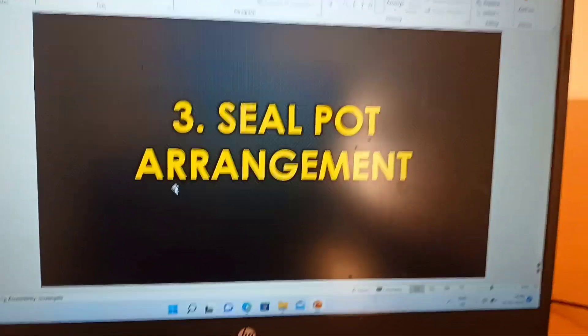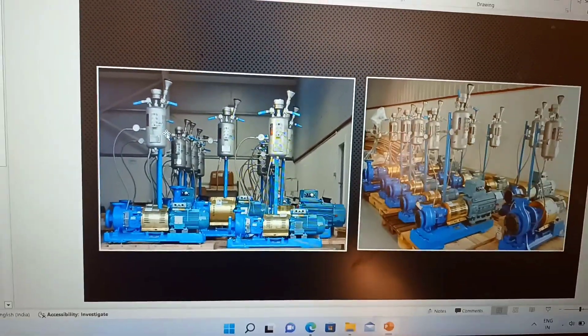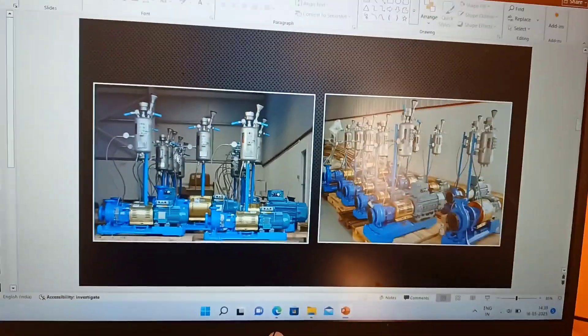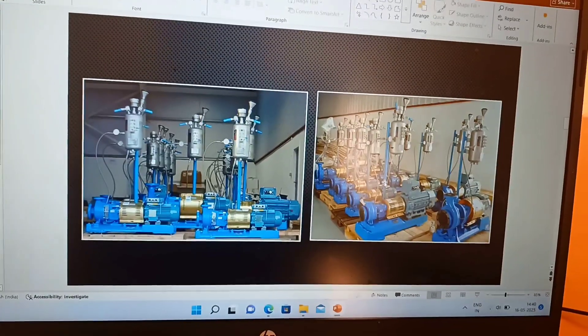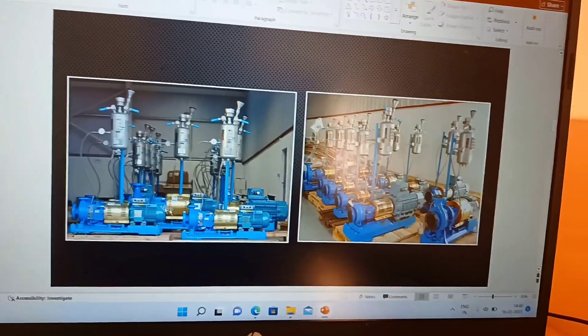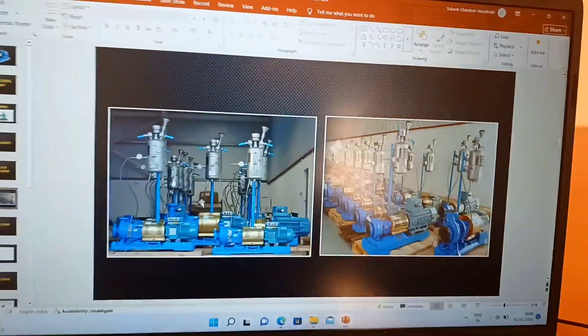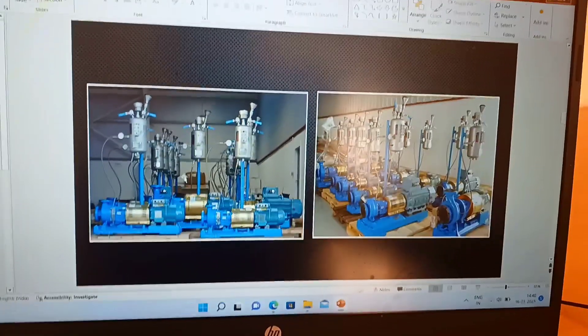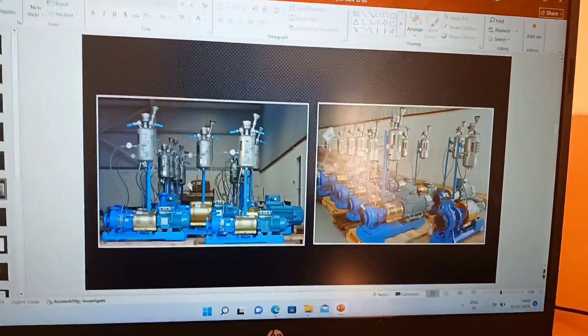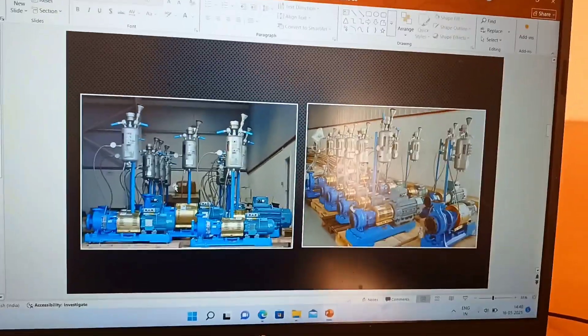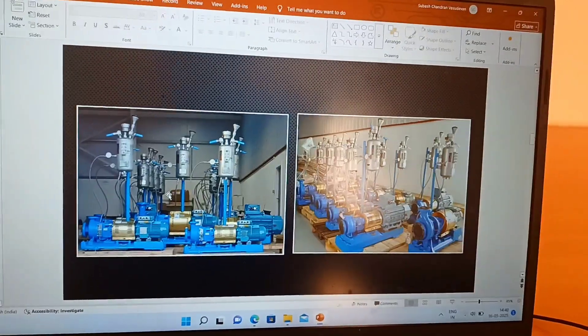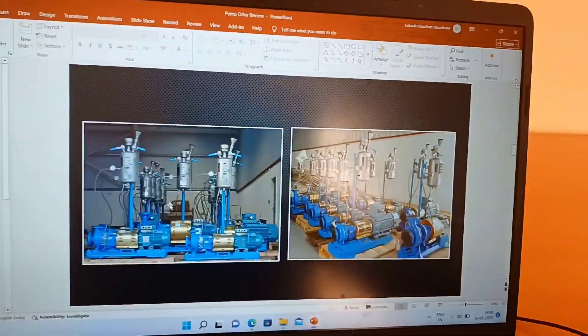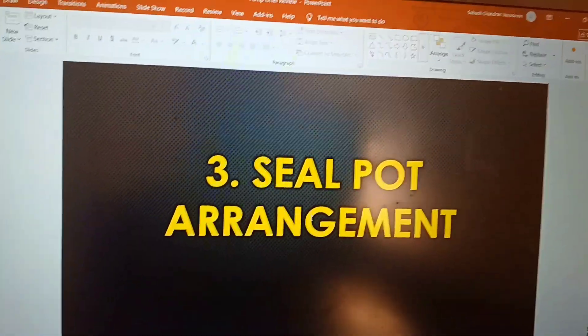The third point is the seal pot arrangement. Pumps come with a seal pot arrangement — for smaller pumps it is compact, but for bigger pumps the seal pot will be larger and mounted on a structure, requiring minimum and maximum distance provisions from the pump. The vendor must provide these details because this impacts the sizing of your pump shed. If the seal pot requirement increases the overall footprint beyond what you have considered, it will also impact the civil foundations.